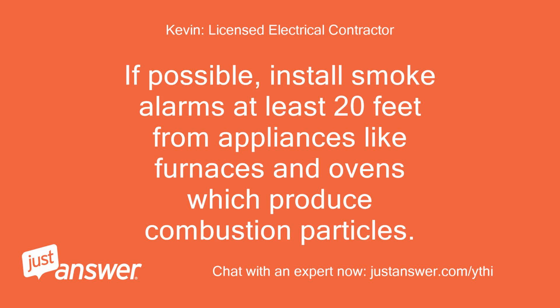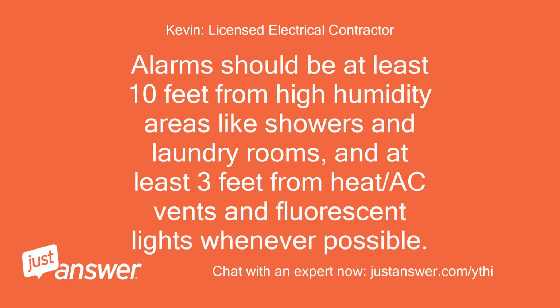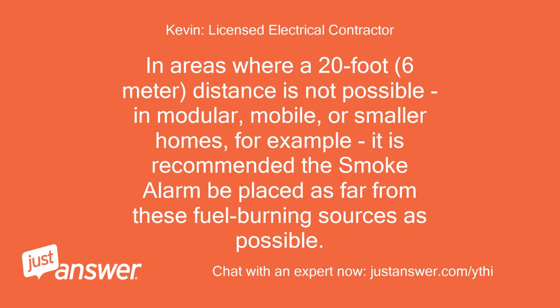If possible, install smoke alarms at least 20 feet from appliances like furnaces and ovens which produce combustion particles. Alarms should be at least 10 feet from high humidity areas like showers and laundry rooms, and at least 3 feet from heat/AC vents and fluorescent lights whenever possible. In areas where a 20-foot, 6-meter, distance is not possible, for example modular, mobile, or smaller homes, it is recommended the smoke alarm be placed as far from these fuel-burning sources as possible.